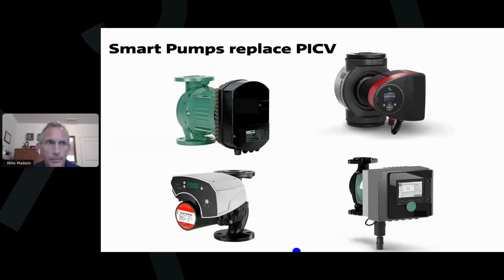But the main question was, if we were going to suggest putting in a VFD to control the secondary chilled water pump, would you say, no, don't just buy a new motor, get a package instead? Is that what you're saying would be even more efficient? I would say if your pumping equipment is at end of life, yes, I would switch to a package. If you just have a motor failure, it's probably more cost effective to put a new motor on. But if your pumps are 20 years old, 15 years old, I would look at replacing the whole pump package. Okay, thank you.